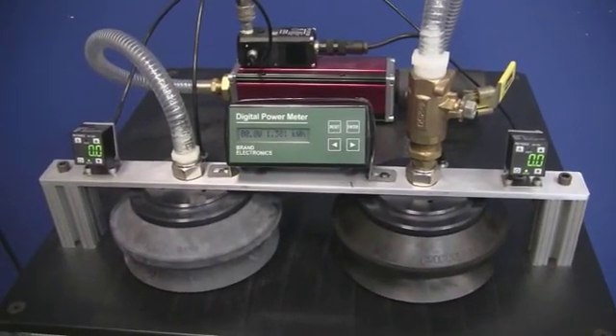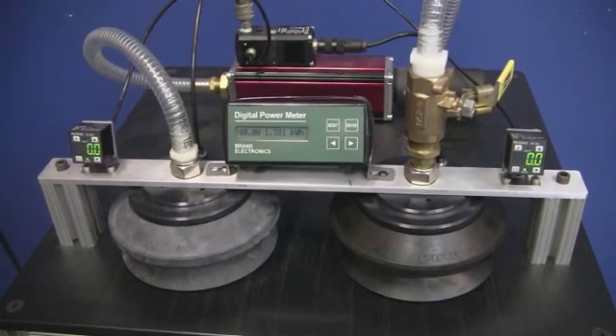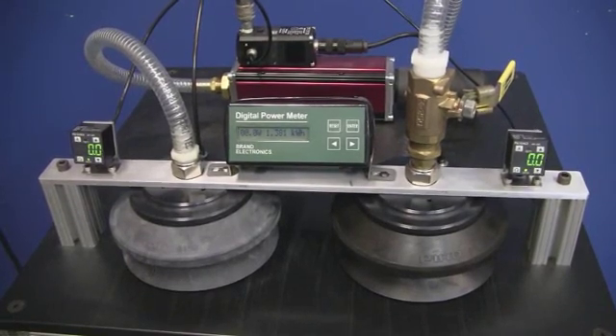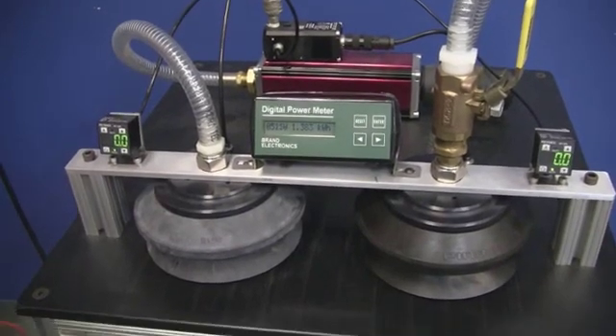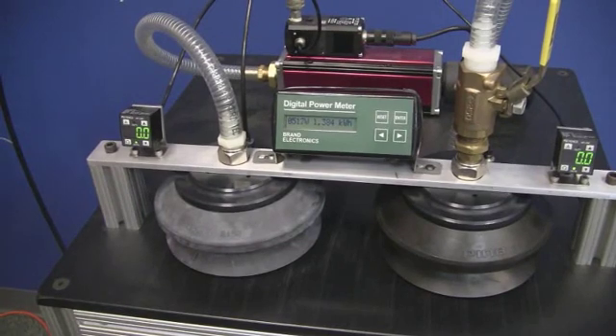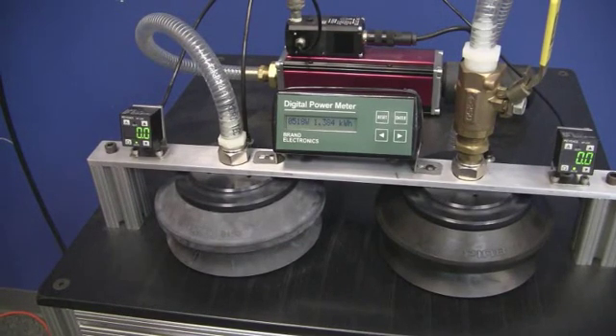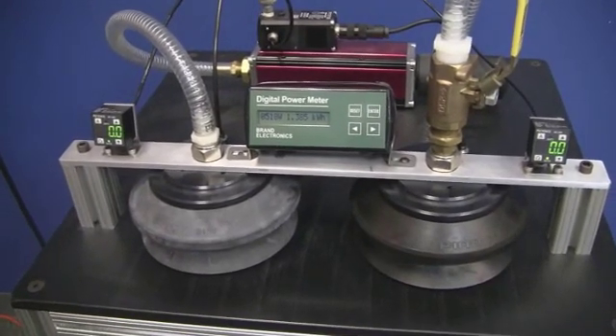This means that the pump consumes energy even when the vacuum is not required. Let's take a look at what the energy does during a typical vacuum cycle. Here when the pump's operating open to atmosphere with nothing on the cup and no load on the motor, it's consuming about 510 watts, which roughly corresponds to the three-quarter horsepower that we saw on the nameplate.